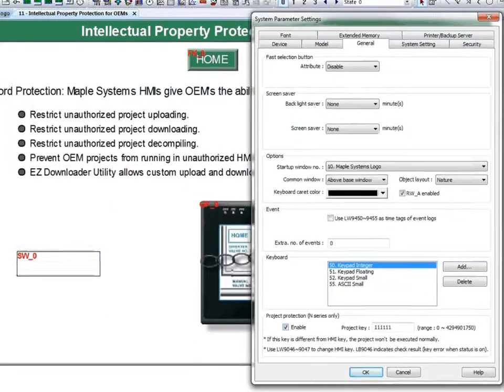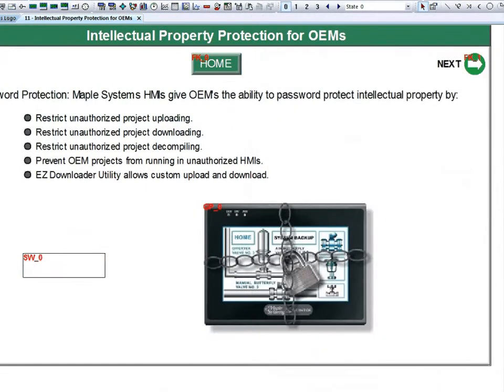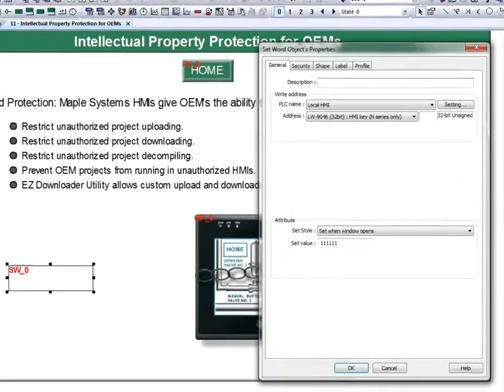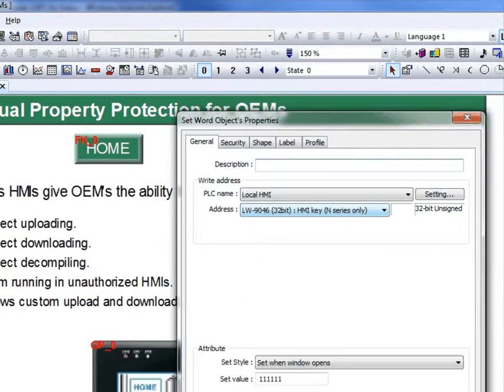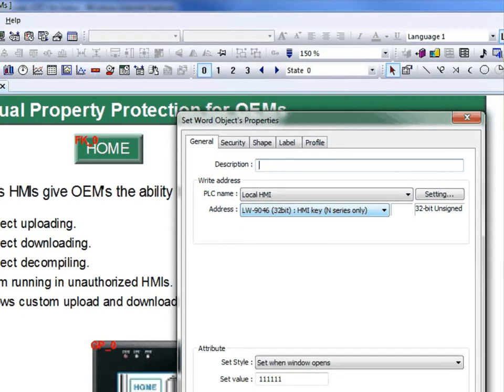To set the HMI key, write the key to system tag LW9046. This will store the key in non-volatile memory. This allows the manufacturer the ability to maintain control over replacement HMIs and system support.